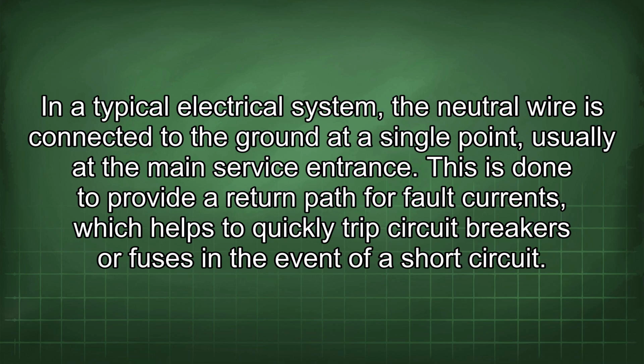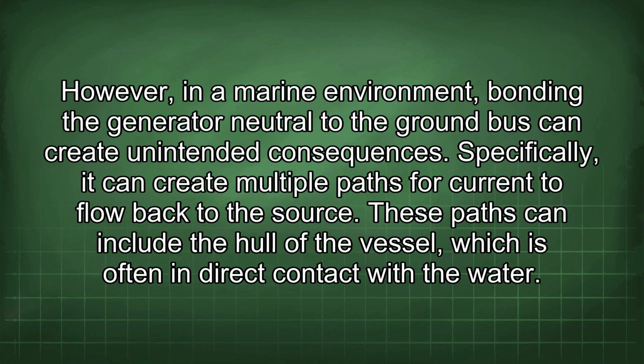This is done to provide a return path for fault currents, which helps to quickly trip circuit breakers or fuses in the event of a short circuit. However, in a marine environment, bonding the generator neutral to the ground bus can create unintended consequences. Specifically, it can create multiple paths for current to flow back to the source. These paths can include the hull of the vessel, which is often in direct contact with the water.